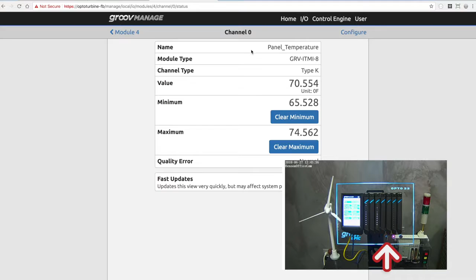This is another example of the smarts in these modules. If I go to configure the module, I can change the name if I wish, and also change the channel type. Let's say I decide to move to a type J thermocouple — I simply select it here and apply the changes, and I'm done. This module provides an array of different thermocouple types and millivolt types, all at your disposal.